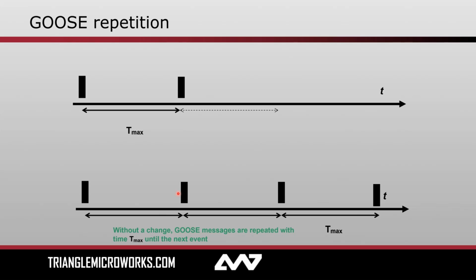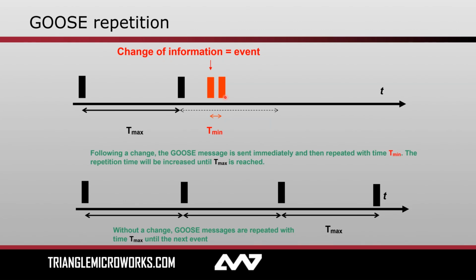As a change eventually occurs, instead of waiting for this entire time, Tmax, immediately within that 2 to 3 millisecond range, I will publish that information out on the wire. And instead of again waiting for time Tmax, I now republish that information again at time Tmin. That time will eventually decay. Instead of continuing to publish at that rapid rate, it will gradually slow down until eventually we reach back to steady state. What this results in is a flurry of messages clustered very close together in case one of them is lost in transit. And then afterwards, as things settle down and data stops changing as rapidly, we come back to the steady state that we had here.